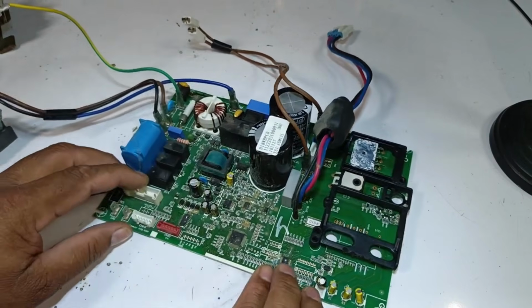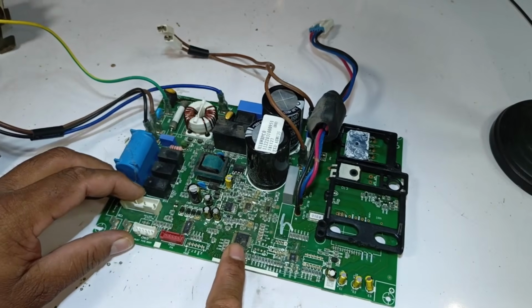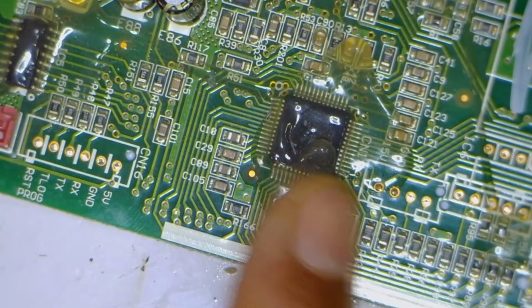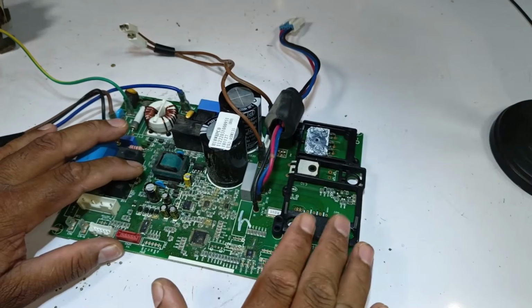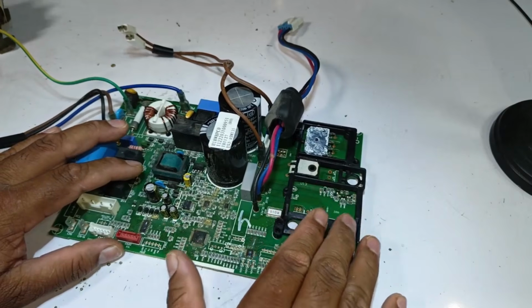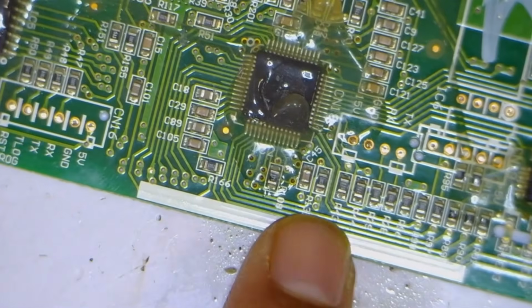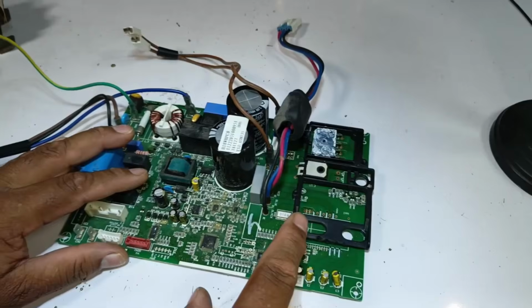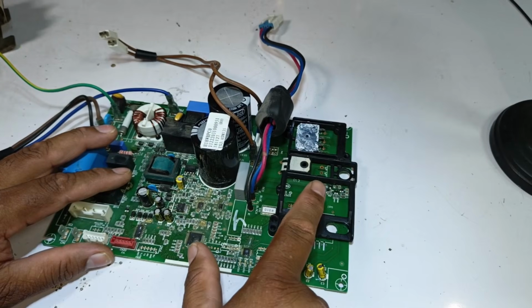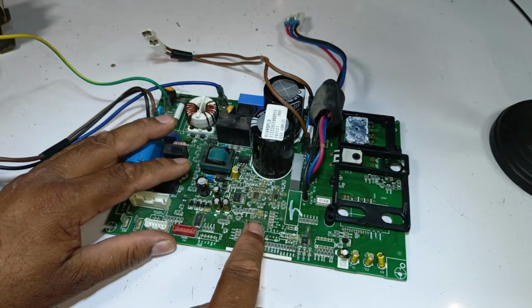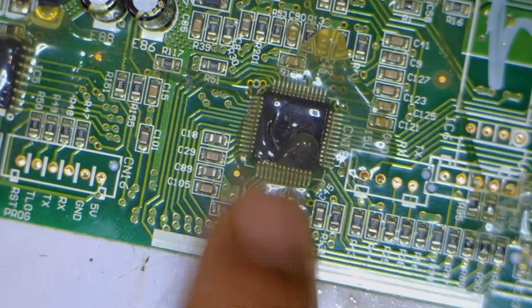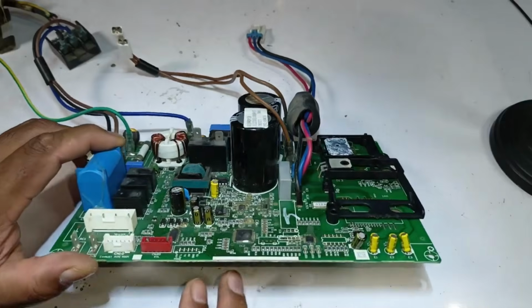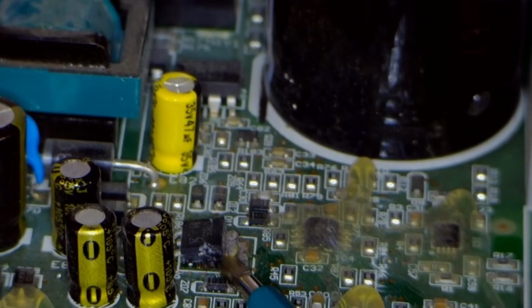However, there is still work remaining, which is to check the microcontroller again to confirm if it is still short-circuited. This is essential since the IPM and IGBT were previously short-circuited, and it's possible they were causing the microcontroller to show a short circuit. If the microcontroller still shows a short circuit even without the IPM and IGBT, it will be necessary to replace the microcontroller. Also, someone had already worked on this PCB before - there is a 5-volt voltage regulator which has been removed, and its ground side has been moved to the top.